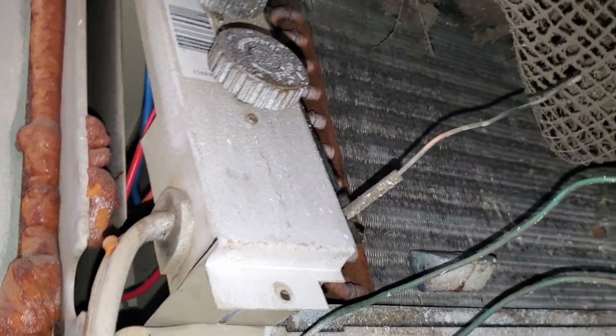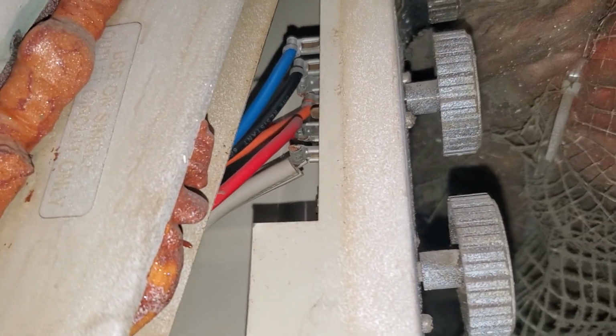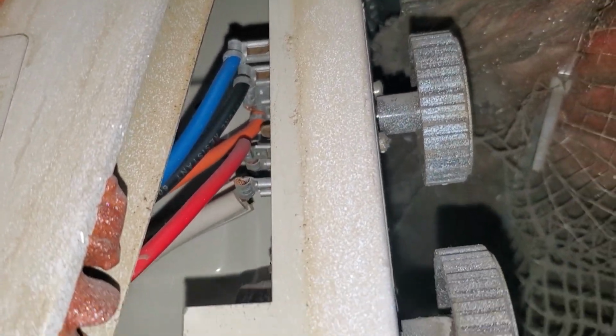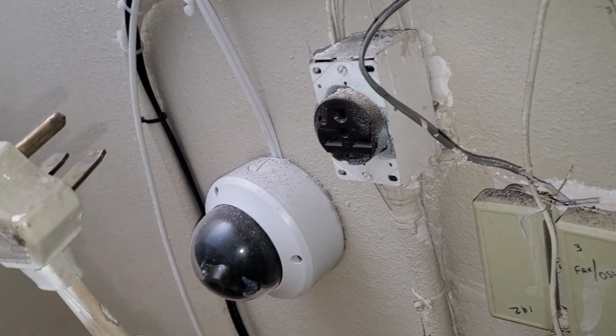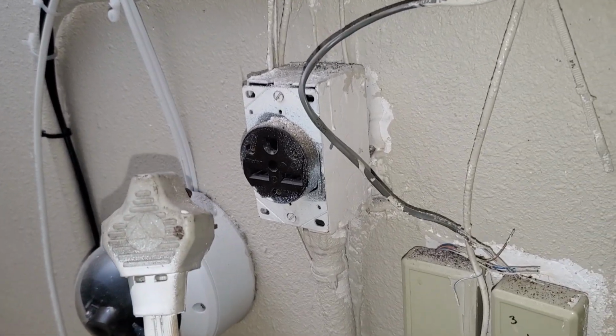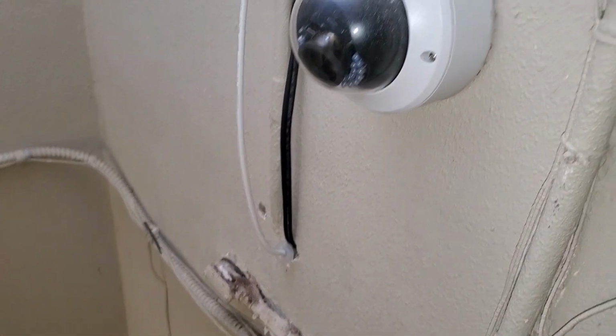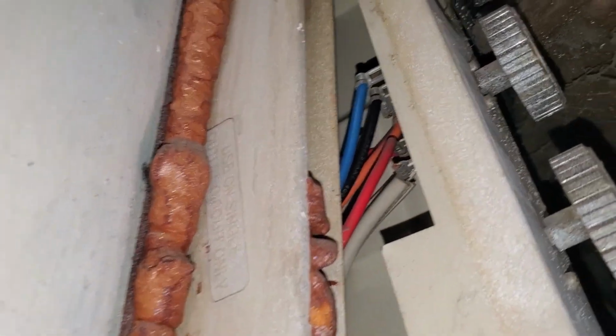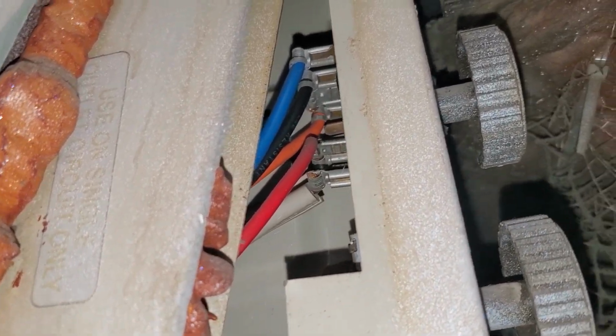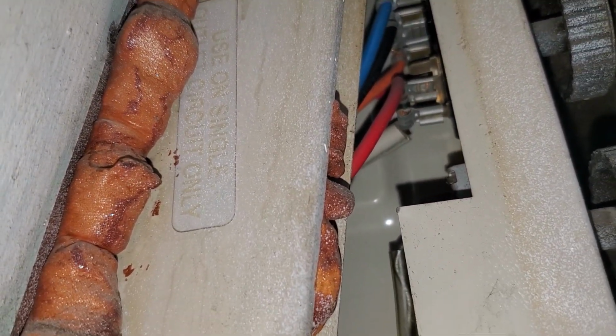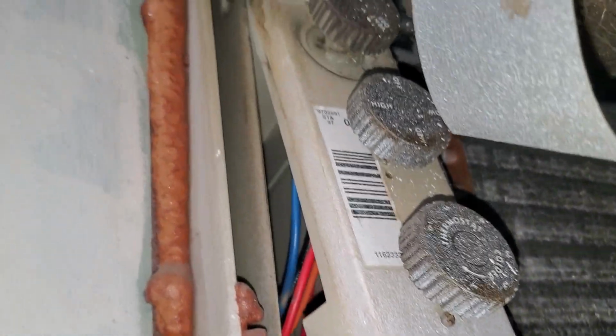It's kind of a hodgepodge, but tracing this back, I was trying to see what voltage this unit was and couldn't find anything on the data tags indicating it. Opening it up, it's connected for 208 volts - it's a 208 volt plug and receptacle, but only 115 volts is going to it since one leg is disconnected inside. That tells me it's a 208 volt window unit, and something's going on. Nothing's a direct short to ground, but I don't know why the power's disconnected.